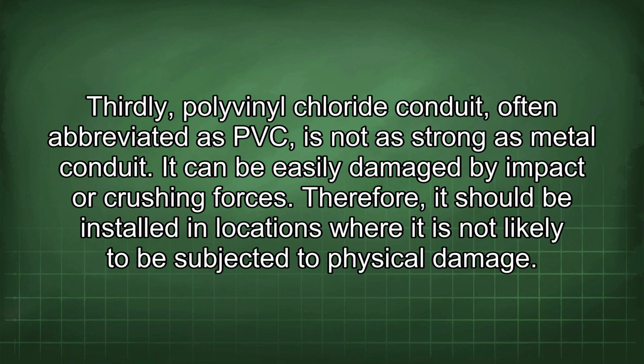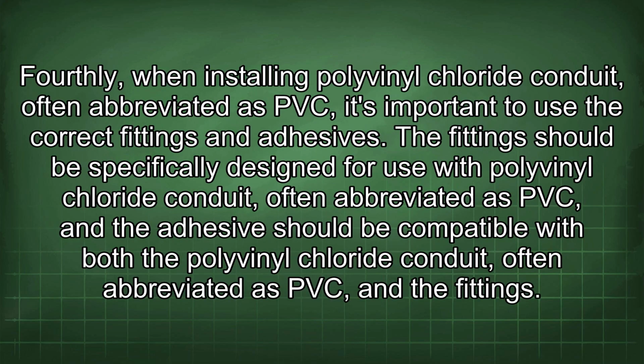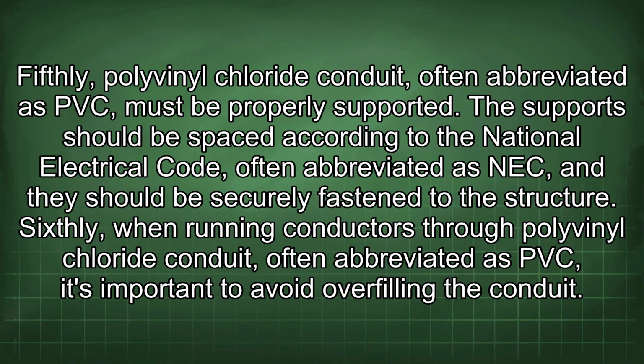Thirdly, PVC is not as strong as metal conduit. It can be easily damaged by impact or crushing forces. Therefore, it should be installed in locations where it is not likely to be subjected to physical damage. Fourthly, when installing PVC, it's important to use the correct fittings and adhesives. The fittings should be specifically designed for use with PVC, and the adhesive should be compatible with both the PVC and the fittings. Fifthly, PVC must be properly supported. The supports should be spaced according to the National Electrical Code, often abbreviated as NEC, and they should be securely fastened to the structure.